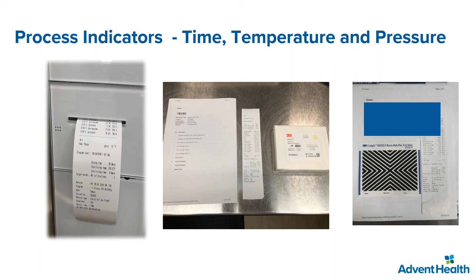Also, we are going to talk about the other way of quality control, which are the biological indicators that are run with the first load of every day at a minimum, and more often if the sterilizer manufacturer indicates a more frequent process. Each type of sterilizer has its own spore testing. These are live spores. These are microorganisms. Spores are one of the most difficult items to kill, so that's why we are using spores to verify that the process inside that chamber was done properly and nothing is alive.